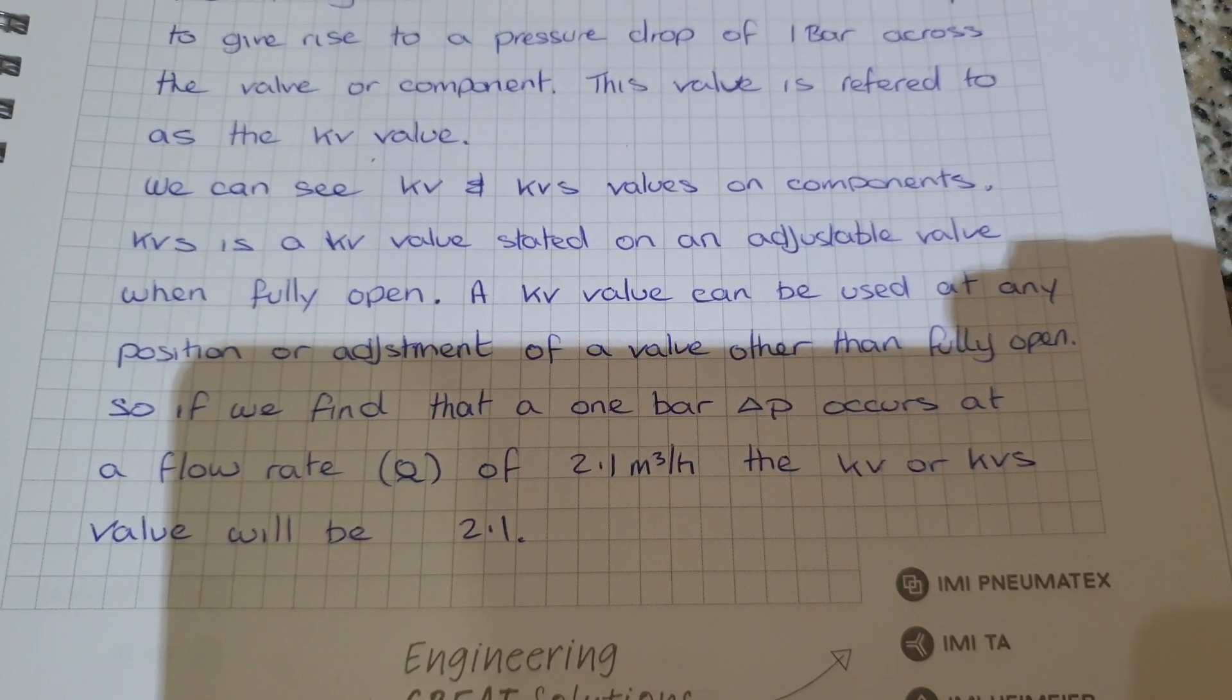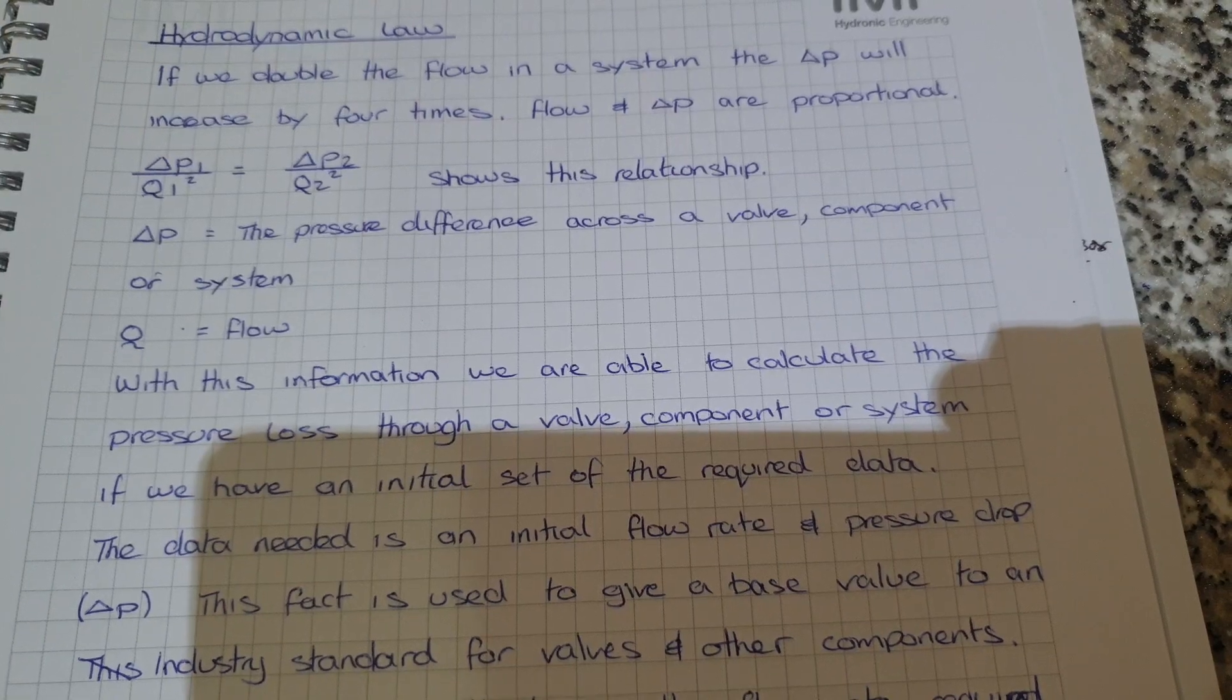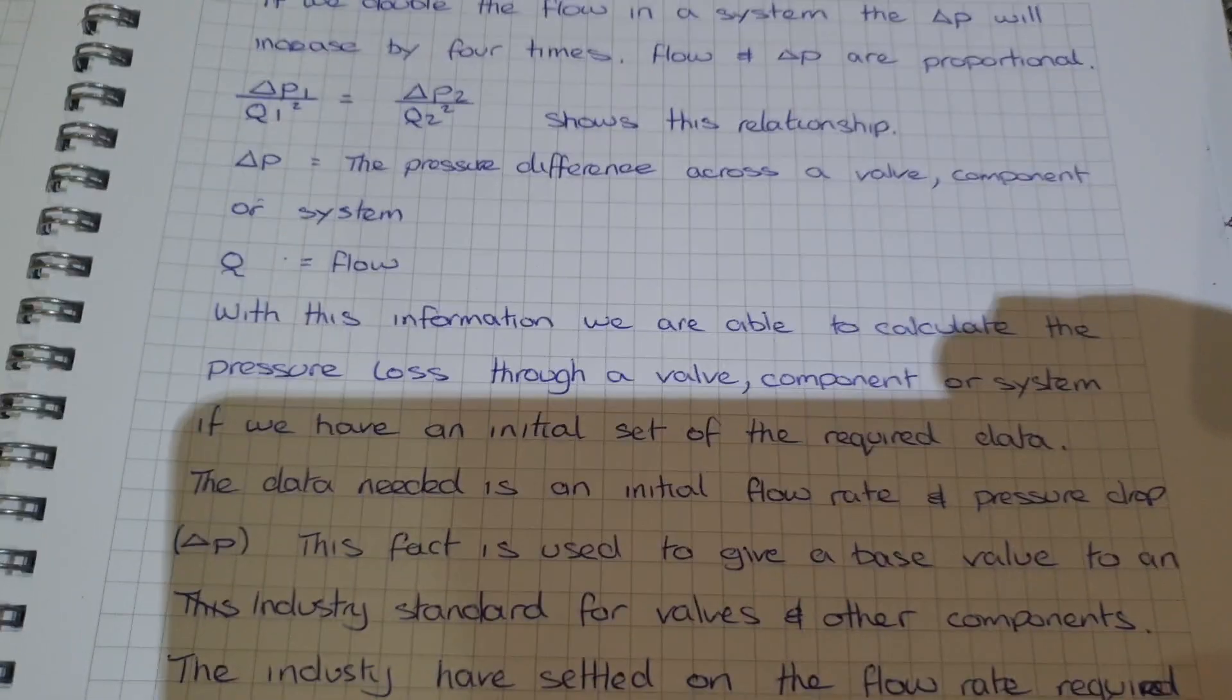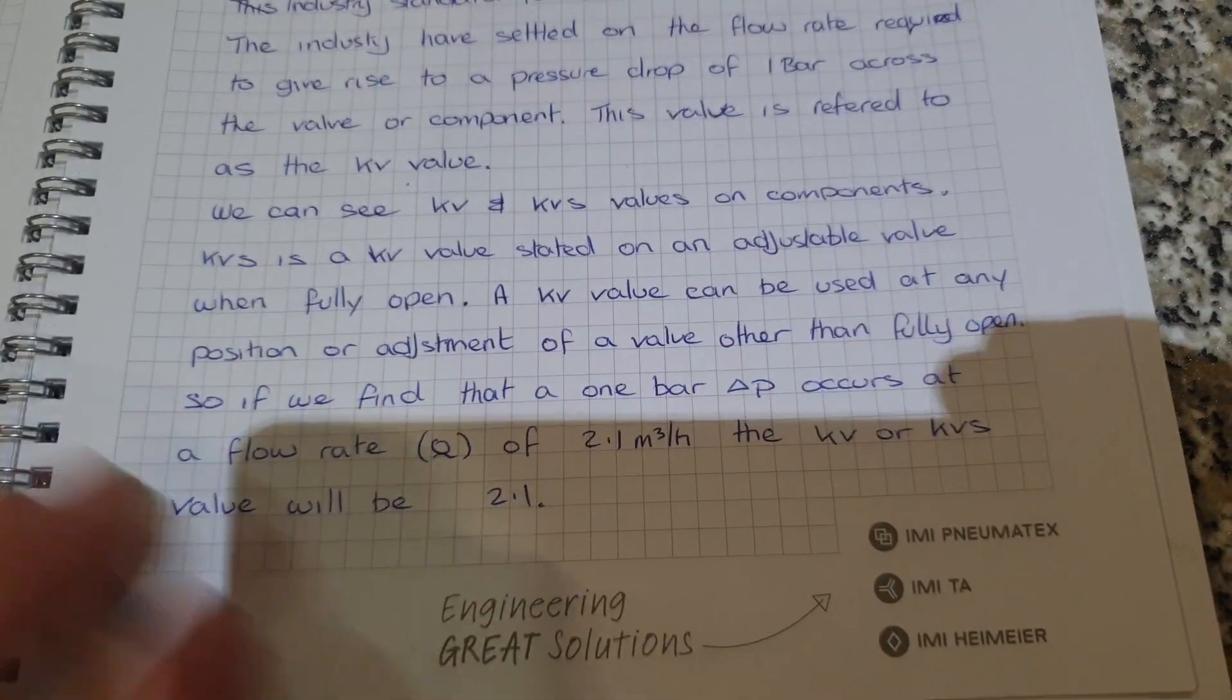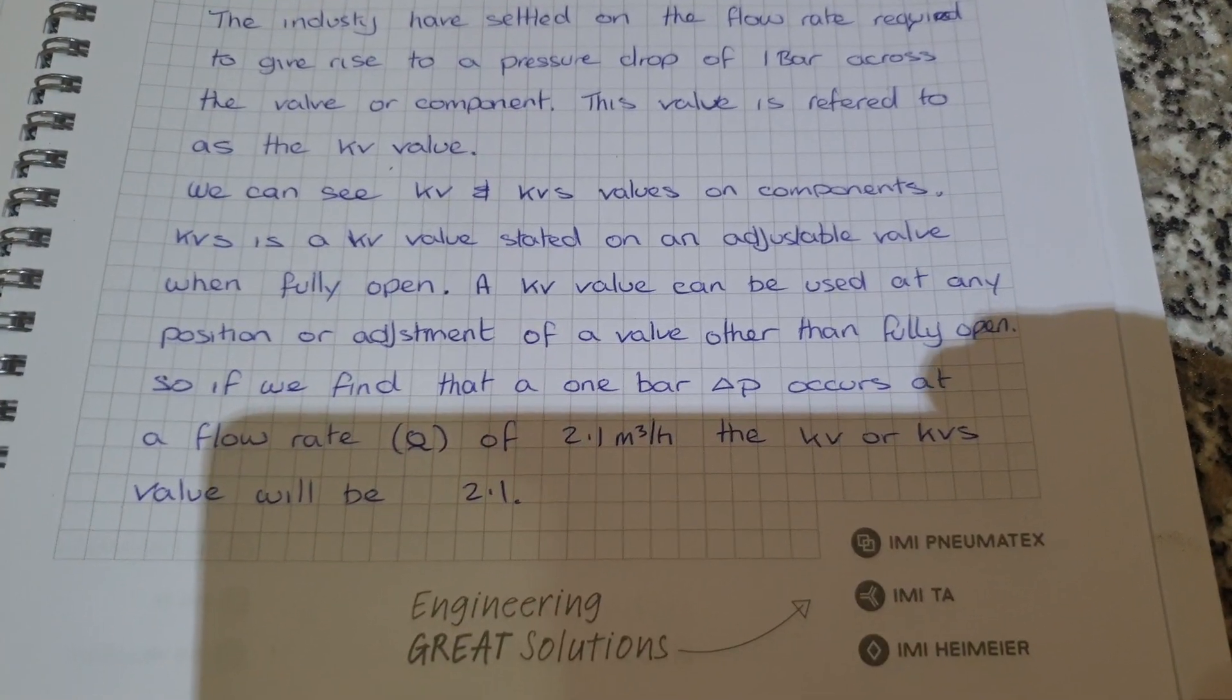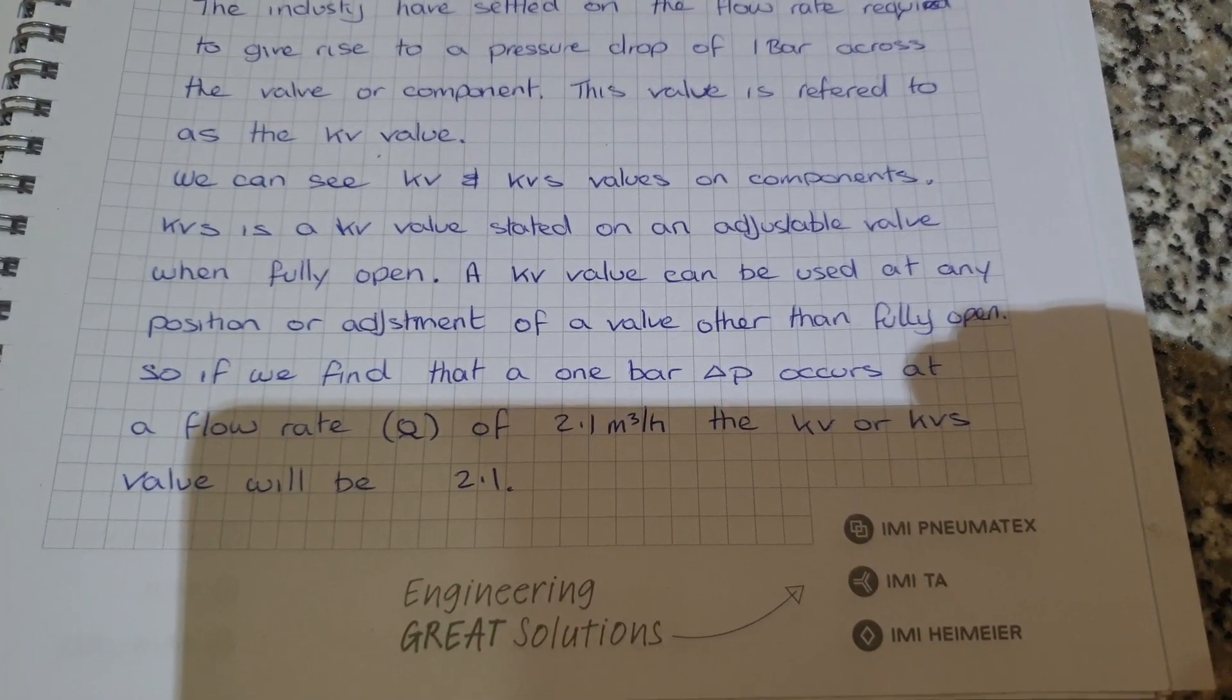Basically, the KV value is used in the industry to give us the base data needed to apply the formula at the top here to calculate the pressure drop that we'll experience at any flow we want to choose. So what we've ended up with here: we've pushed our water through our valve, we've got delta P of one bar, and the flow rate to that point was 2.1 cubic meters an hour, giving us a KV value of 2.1. If it's a control valve and it's fully open, we would call that the KVS value.